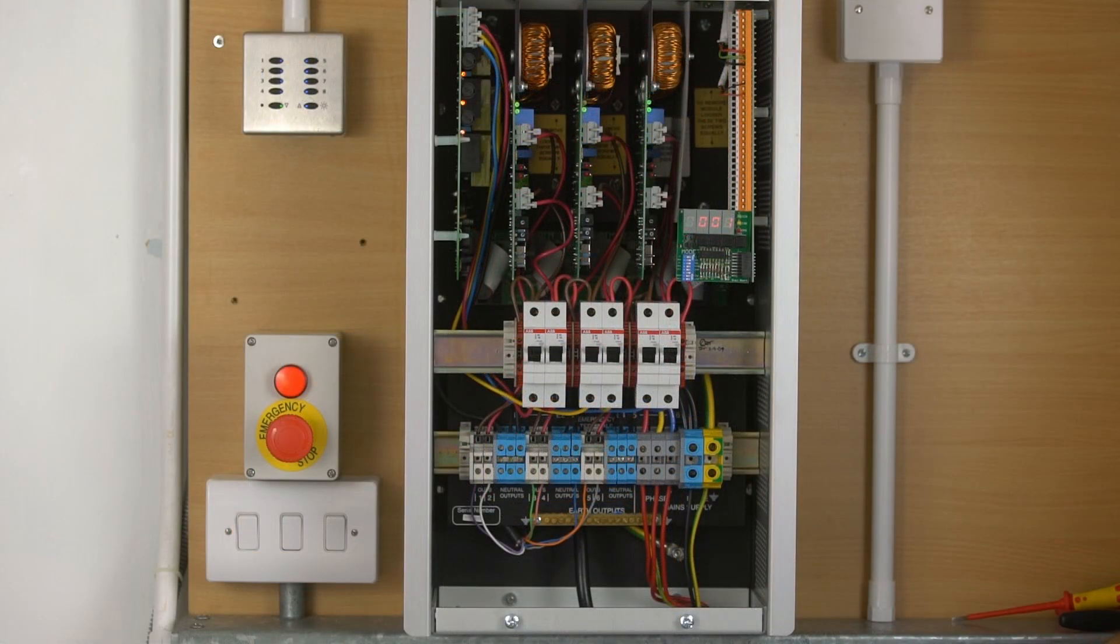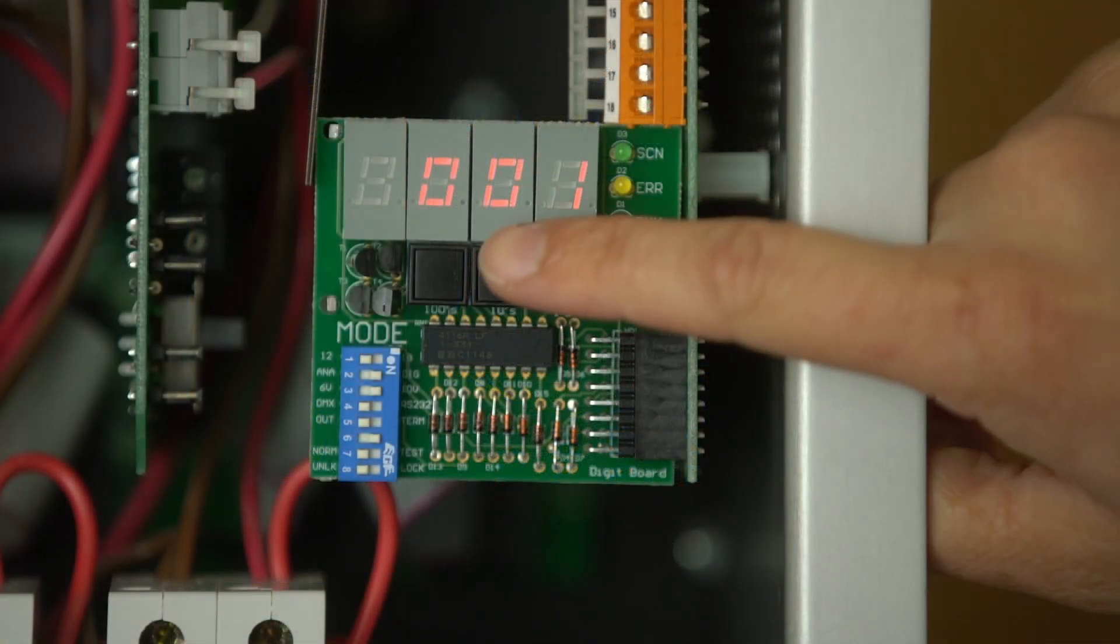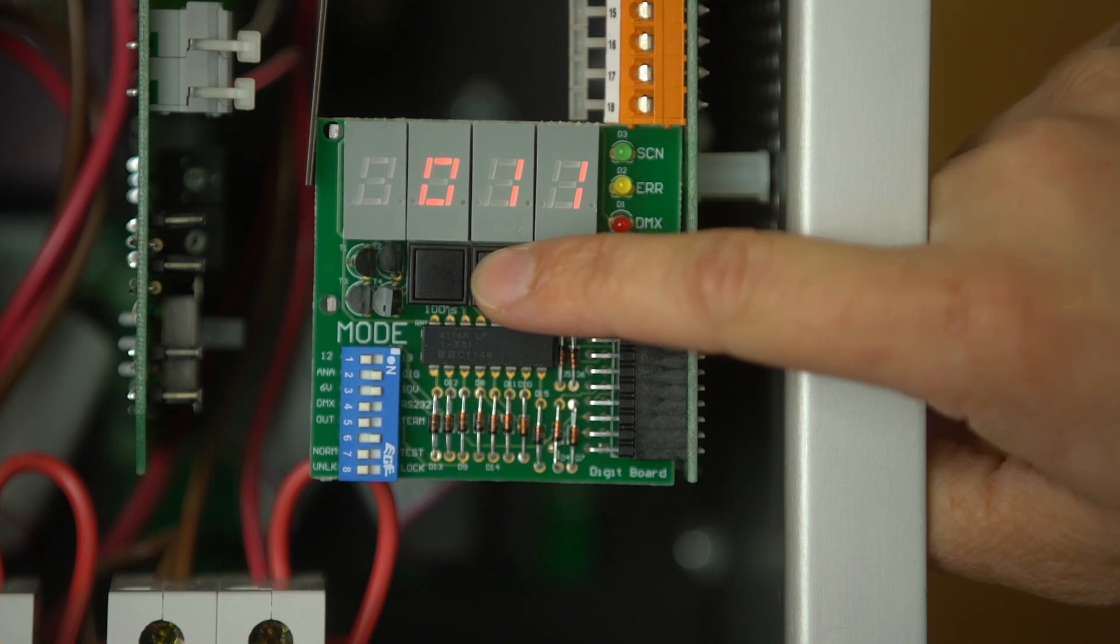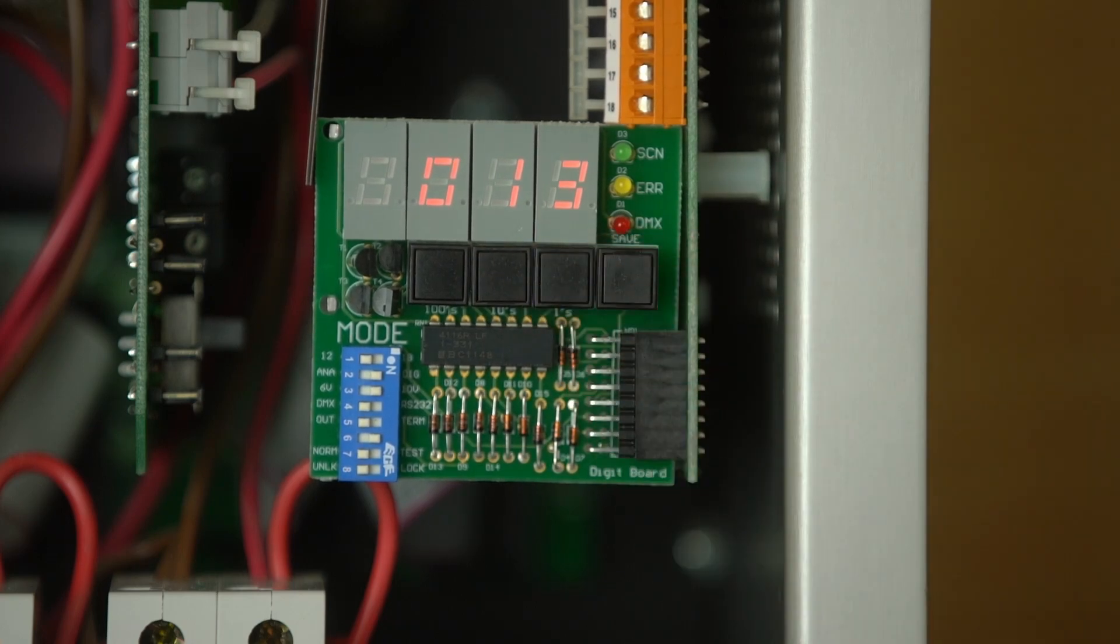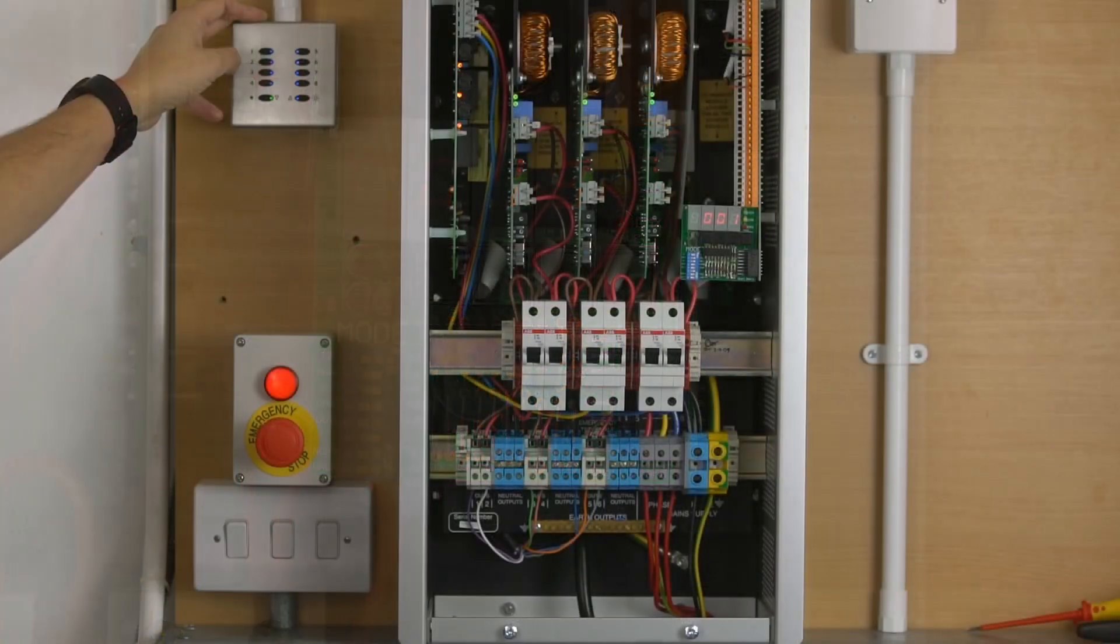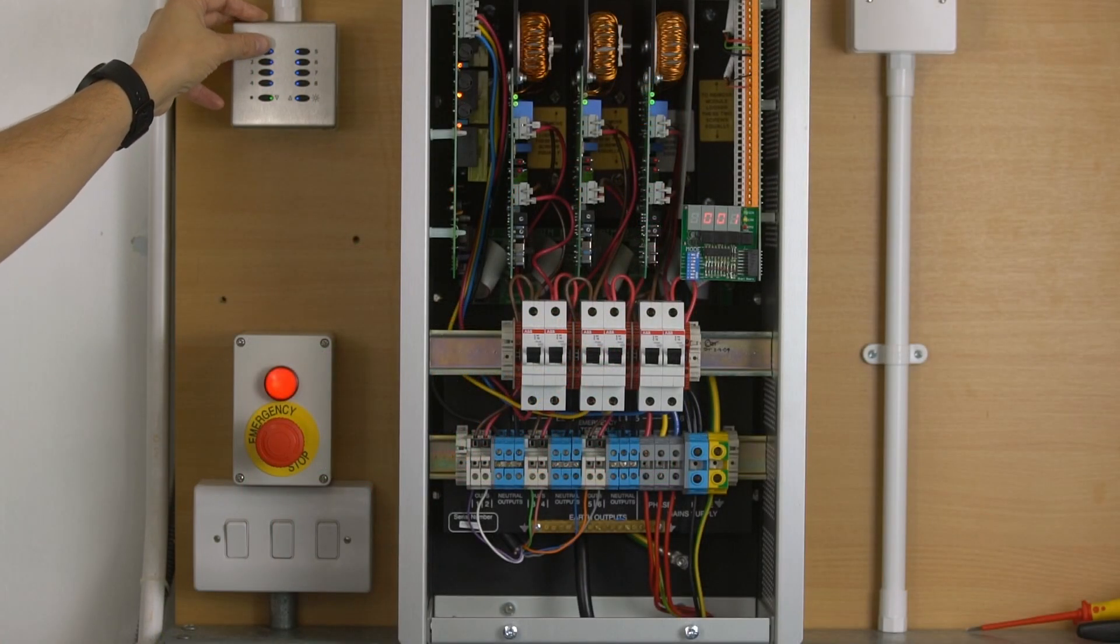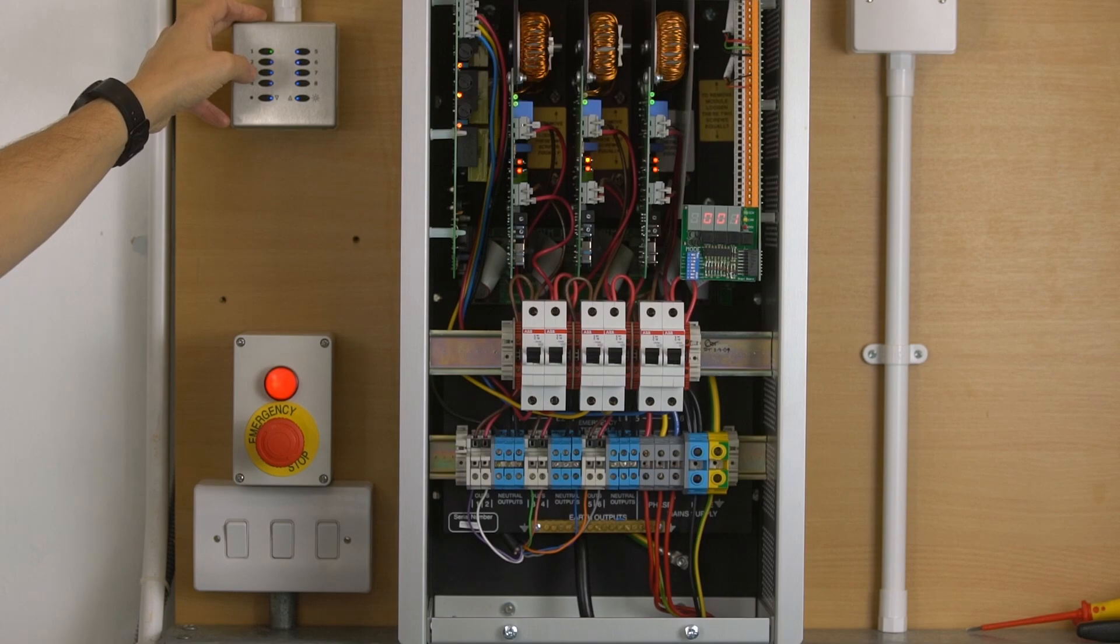Once the system is powered back up again, just check your address. You may need to change this if this is the second or the third pack. There must always be a panel that's on 001. And at this point from the keypad, you should see the system responding correctly.